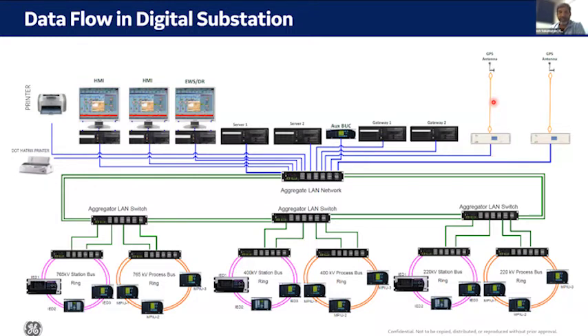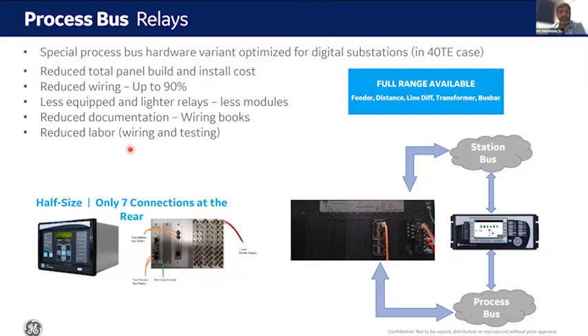A typical process bus relay has hardly any cabling, and the relay size is almost half compared to conventional ones. All cabling resides in the merging unit or process interface unit. The benefit is that wiring in the control room is reduced by almost 90%. Relays are lighter and more relays can be accommodated in one panel, and engineering and labor are also reduced.